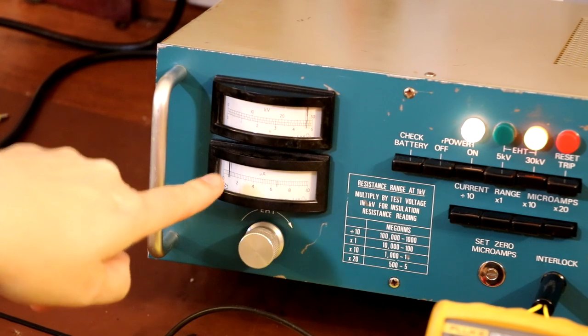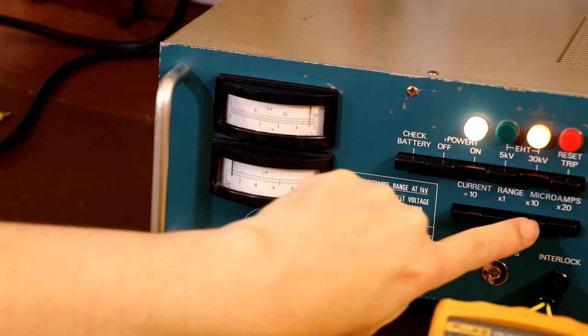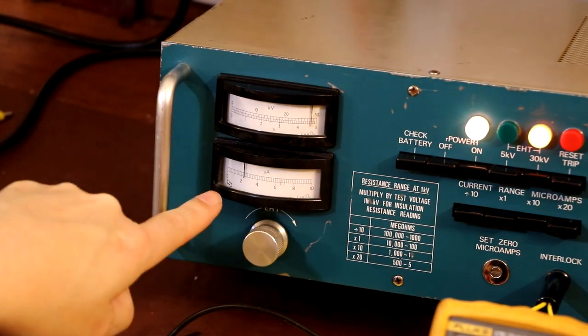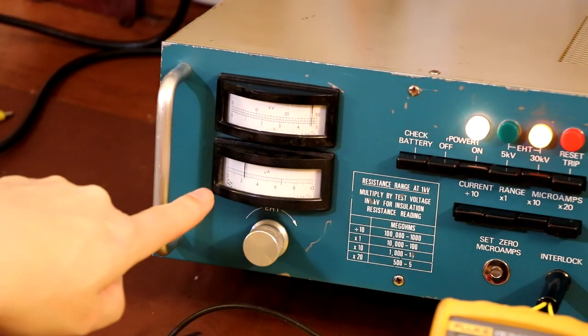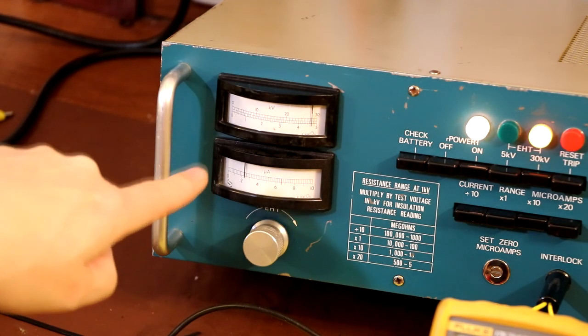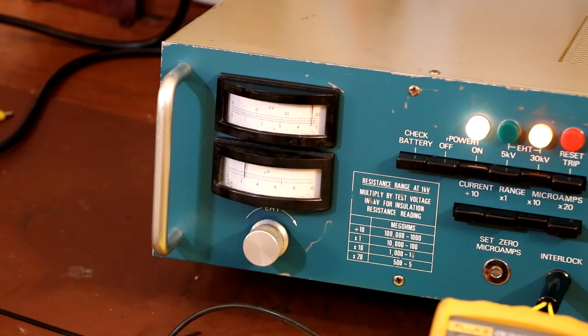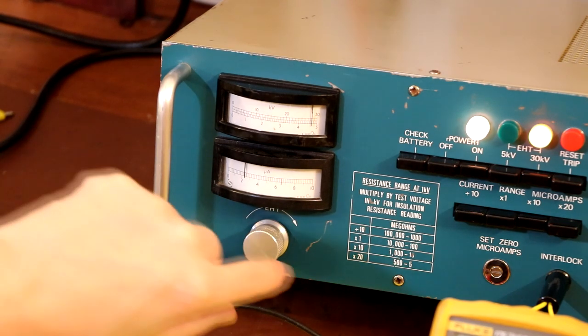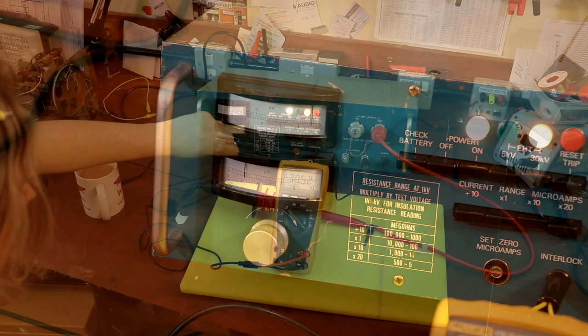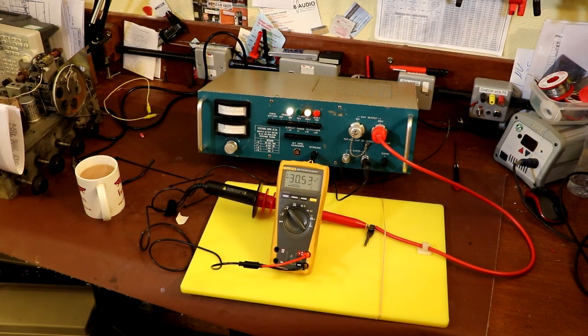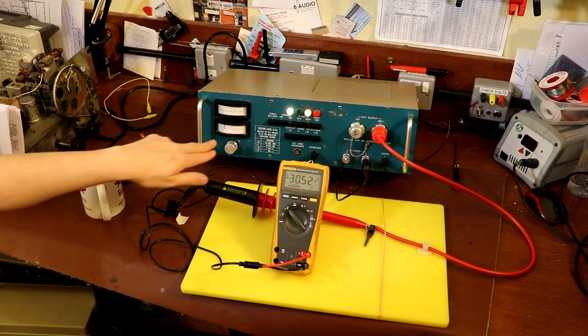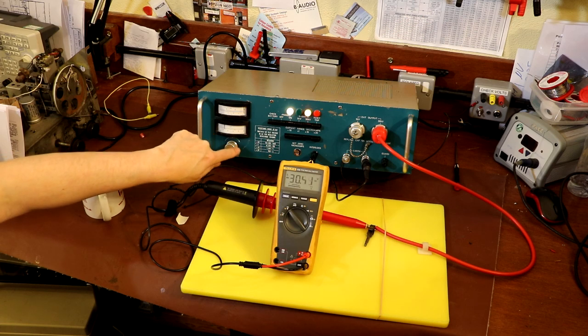It's actually started to increase a little bit. Yeah, and in fact it's gone up quite considerably, so it does show now that we're getting some current leaking to earth somewhere, not exactly sure where. I think we're nearly at full voltage now. Okay, so we're at 30,000 volts now, and everything seems to be withstanding, but we are drawing some current from the power supply, so we've definitely got some leakage to earth.